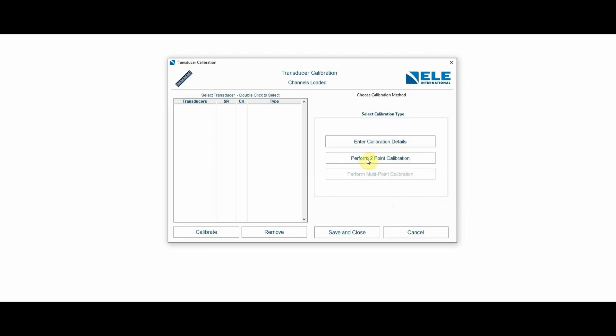I have the option to either do a two-point calibration, for which I would need calibration equipment, or I can simply enter calibration details. In this case, I'm going to enter the calibration details that have shown up in my calibration certificate.